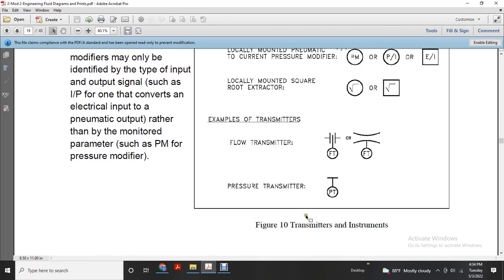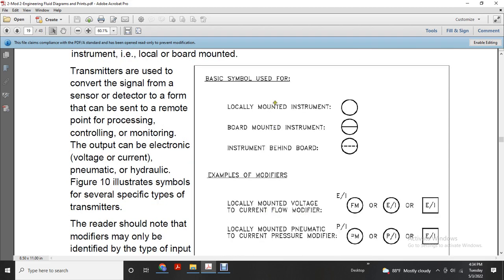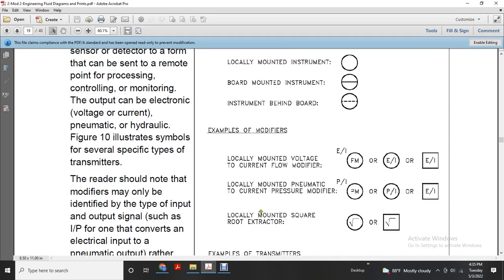Alright, Figure 10 shows your transmitters and instruments. Basic symbols: you have a locally mounted instrument, a board mounted instrument, and an instrument behind the board. Examples of modifiers: a locally mounted voltage-to-current modifier, shown as E/I, or volts over amps; a flow modifier in two or three different structures, circles and squares. A locally mounted pneumatic current-to-pressure modifier, P over I, or PM, pressure over I. Electric voltage locally mounted square root extractor: a circle with the square root sign.